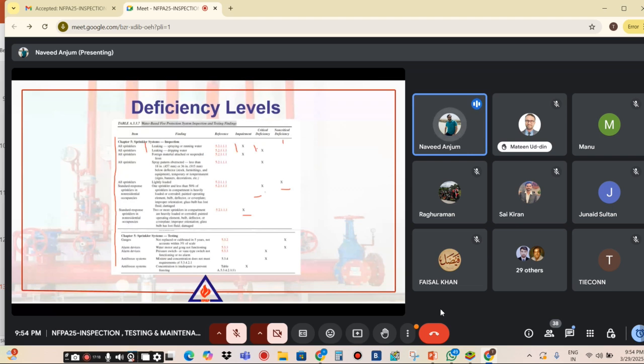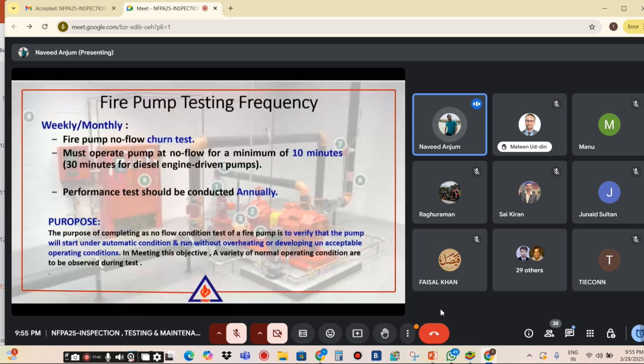I already told you that the fire pump is really important. Because of this, firstly I am discussing the fire pump. Basically, we have to test our fire pump every week as per NFPA, and they also give an option of monthly testing, but it is just for electric pumps. As per manufacturer instructions and some other requirements, on that basis they can allow you monthly. Otherwise, mostly they will tell you that you have to check the fire pump on a weekly basis, both electric pump and diesel pump.